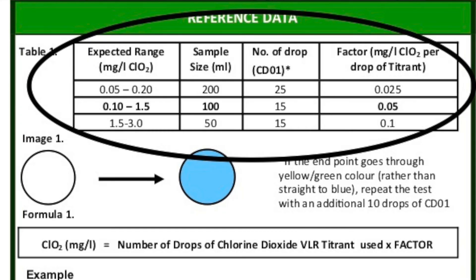The chlorine dioxide concentration is calculated by multiplying the number of drops by the factor based on the table shown. For example, 10 drops of VLR titrant times a 0.05 factor equals 0.5 ppm as ClO2.